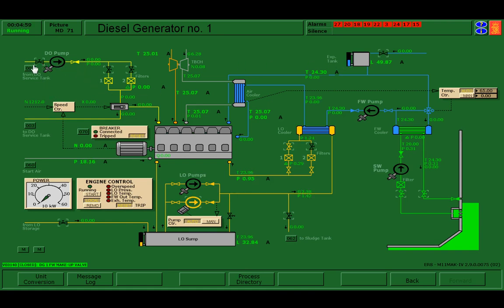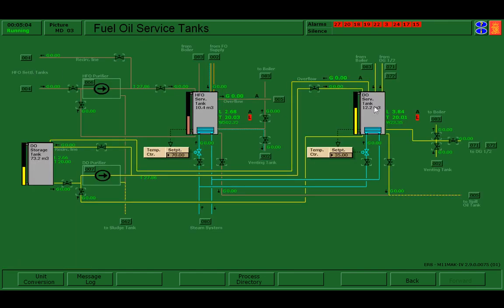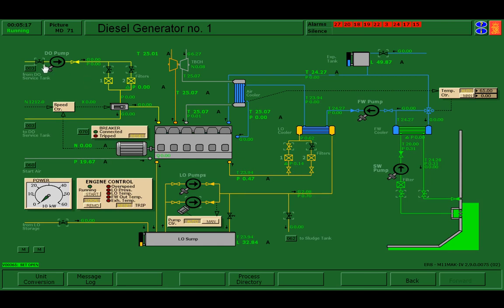On the fuel side, I'm going to go to my starting point for fuel on page number 3. My diesel oil service tank. I have a pathway to go to my diesel generator 1. I have a supply valve and a filter 1 valve. As long as your pressure is above 15 bar, then we are okay at this point to start our diesel generator number 1. I'm going to start him.